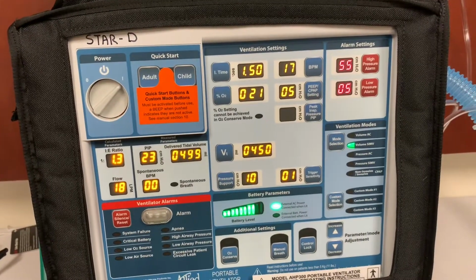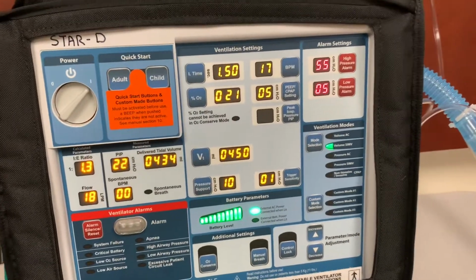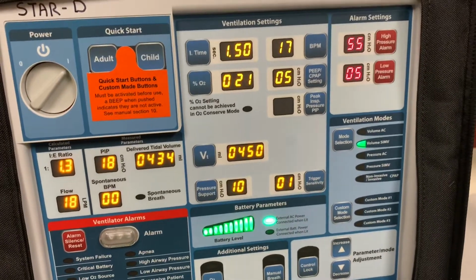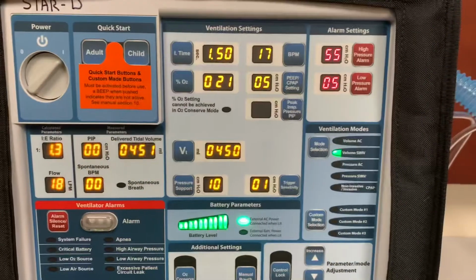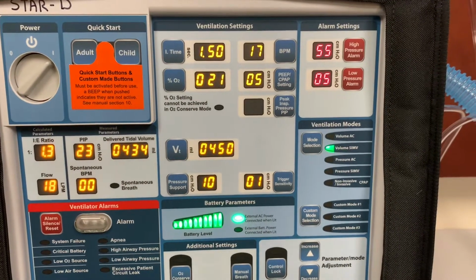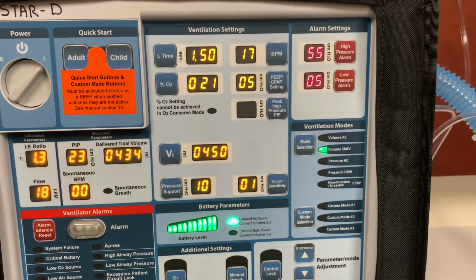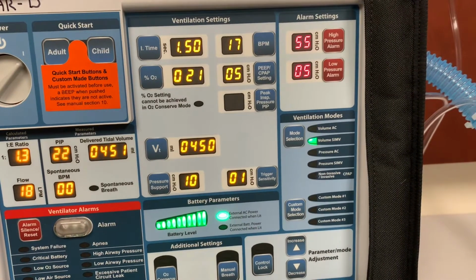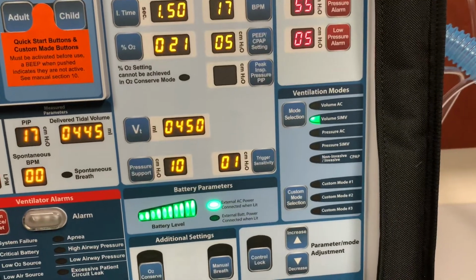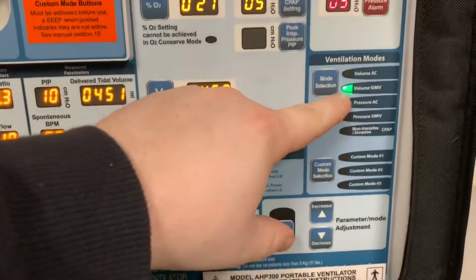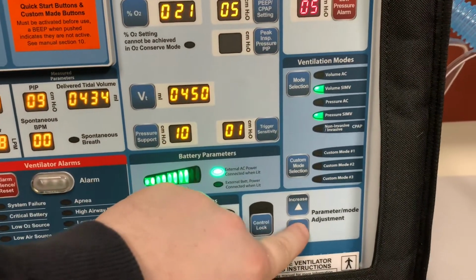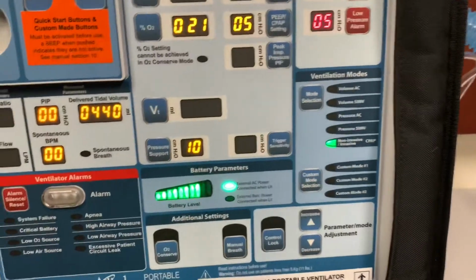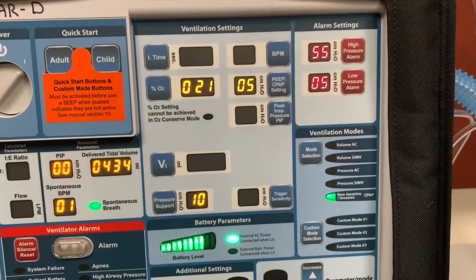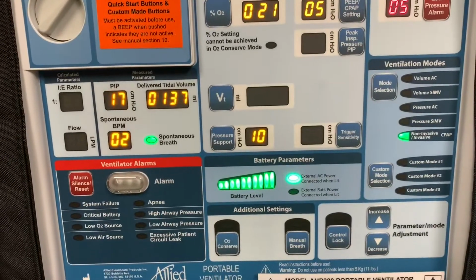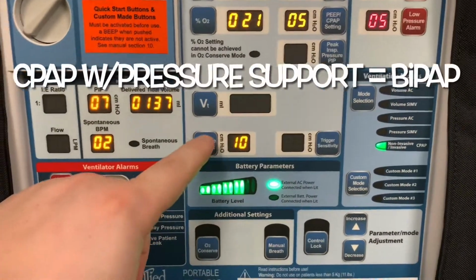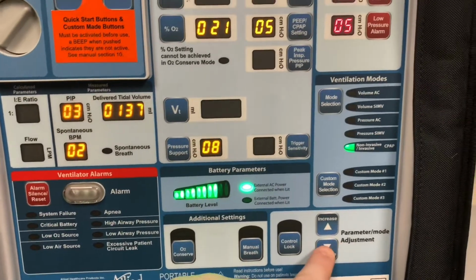You can adjust anything from tidal volume, inspiratory time, oxygen percentage, PEEP and CPAP settings, as well as CPAP with pressure support. Star Ambulance paramedics should be able to limit their mode usage with this device to simply 2: volume SIMV for intubated patients, or CPAP with pressure support. So volume SIMV, you can always change that. Now you go to CPAP, which at this point is just 5, with a pressure support of 10. So therefore this is actually CPAP with pressure support. To simply make it CPAP, I would get rid of the pressure support.